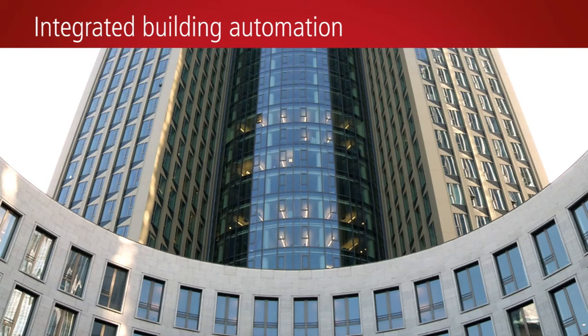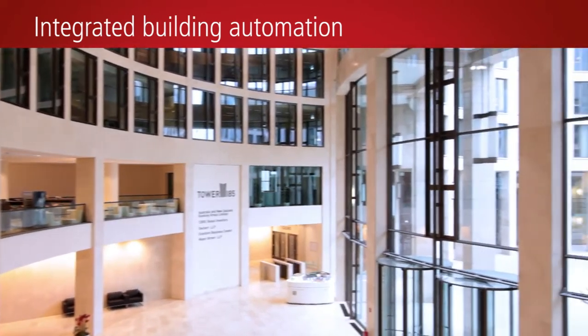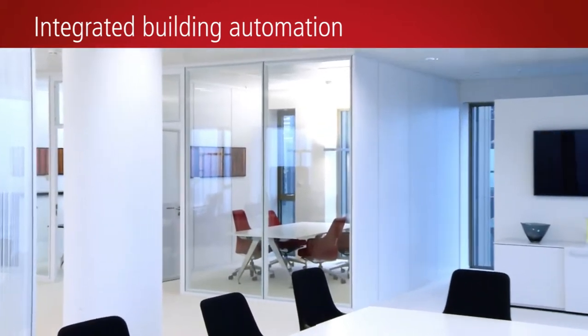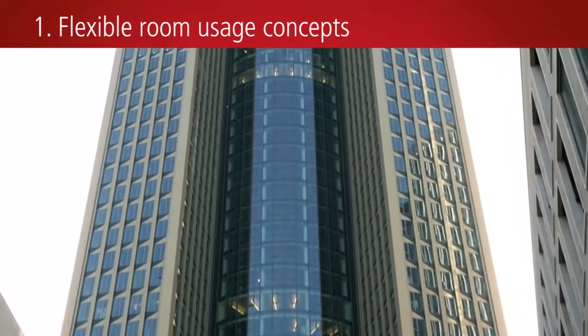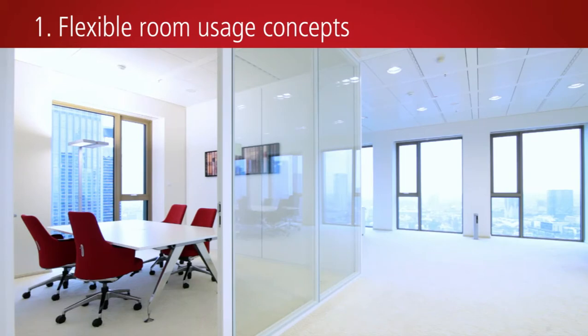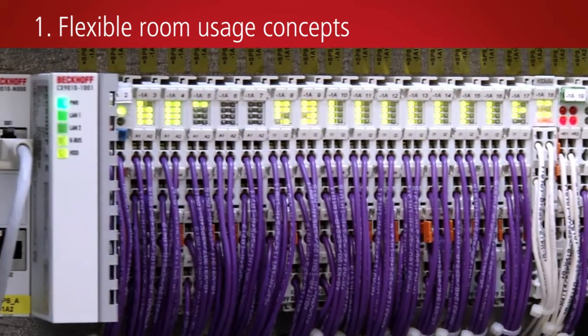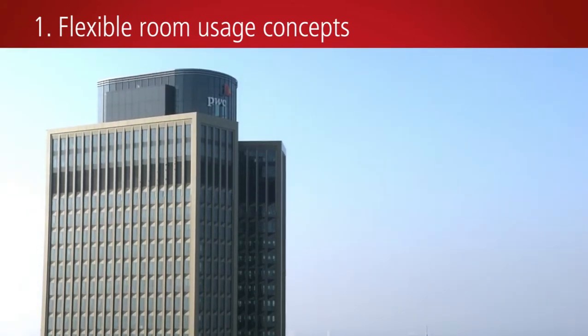The processed data is subsequently forwarded to the building management system level. From the point of view of both the building operator and the various tenants, a modern functional building must be adaptable to changing usage requirements and operable with the least possible use of resources. At the management and operation level, the FIS system from Hermos evaluates all requirement signals to ensure dynamic room management. The building's communication backbone is an Ethernet TCP/IP network consisting of redundant fiber-optic cable rings, with Beckhoff automation technology linked to it floor by floor.